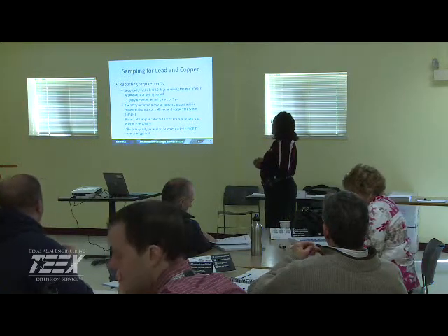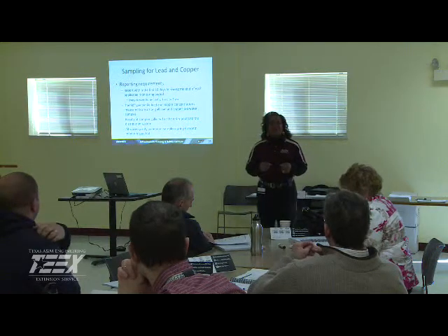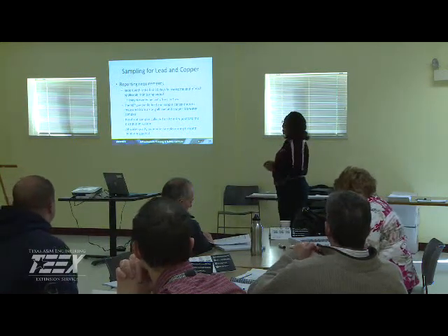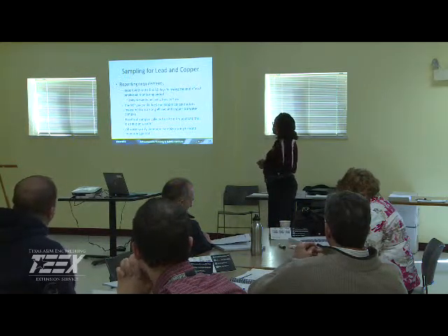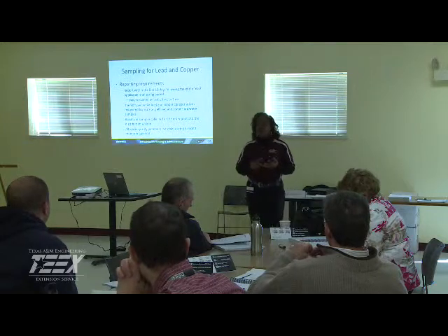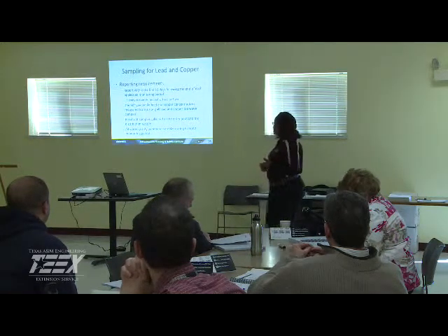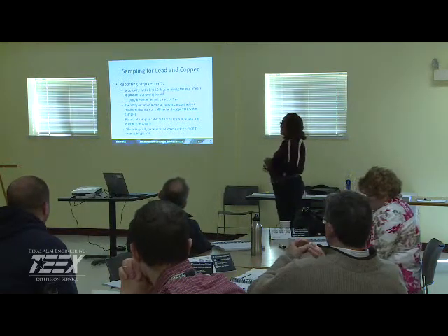Okay. Reporting requirements. And I think Rebecca got this one right. After we get those results back, the report is due within the first 10 days following the end of each applicable monitoring period. So that's either every 6 months, annually, every 3 years, or 9 years. You'll do that within the first 10 days.